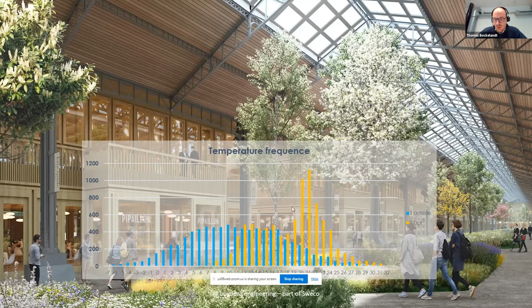This is one of the interesting results of the simulation. Here in blue you can see outside temperatures in a standard meteorological year in Brussels. I presented it this way to the client: since we don't do any climatization, this is the distribution of temperatures one can expect in the large hallway at ground level, where people would be, with a minimum temperature of maybe 8, 9, or 10 degrees. That was considered okay for what was intended to happen there. There's also a large chunk of temperatures around 20-21 degrees, which would have been much higher without the natural ventilation system. The client was happy with this, and we moved forward.